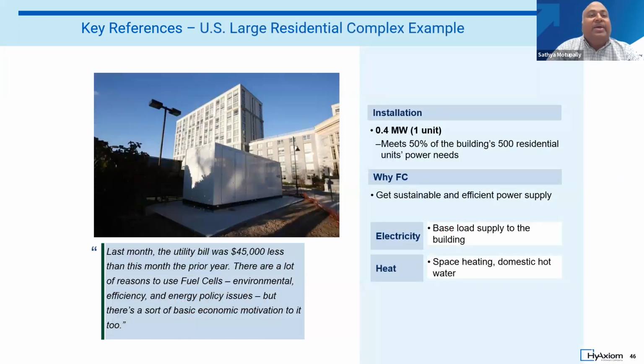I want to go through a few examples before I end. We talked about where our fuel cells are used and why. This is an example of a large US residential complex in Hartford, Connecticut. It has one of our units running in the back of the building, meeting about 55% of the building's 500-apartment load. The entire building also gets its space heating and domestic hot water from our fuel cell. Comparing what this building was paying for electricity before versus now, with the higher utilization of natural gas, we've brought their monthly electricity bills down considerably.